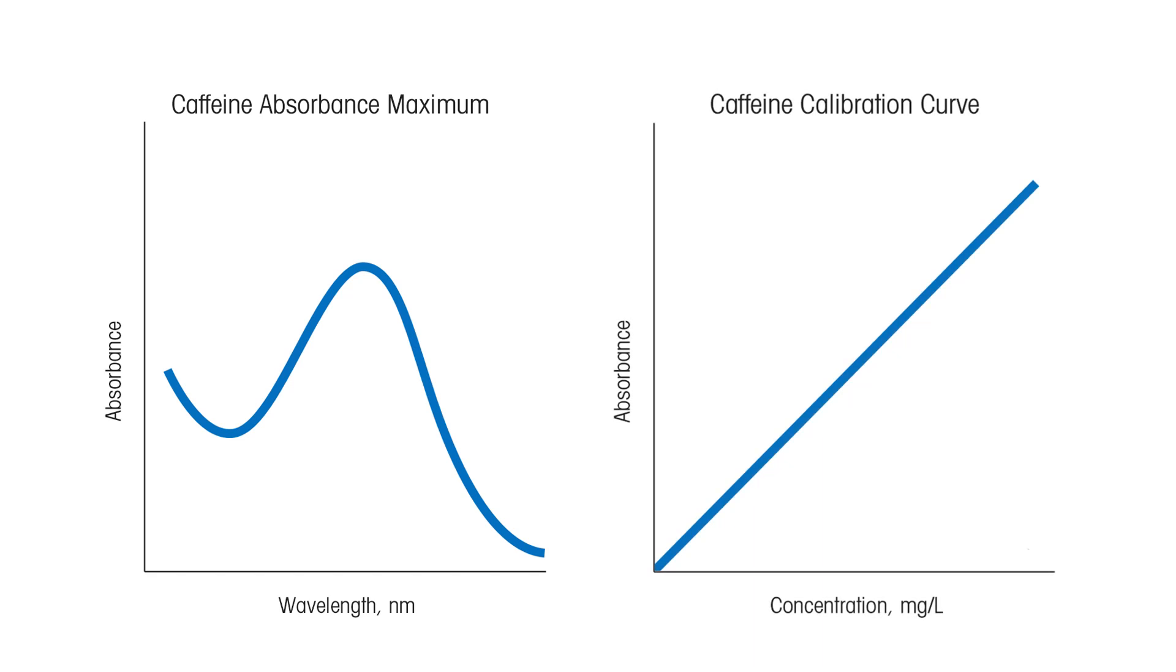Using the pre-programmed calibration curve, which shows absorbance at a particular wavelength against concentration, when we know the amount of light absorbed by the sample at that wavelength, we can determine the concentration. Brilliant!